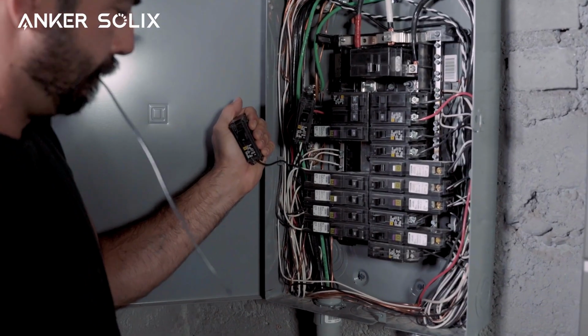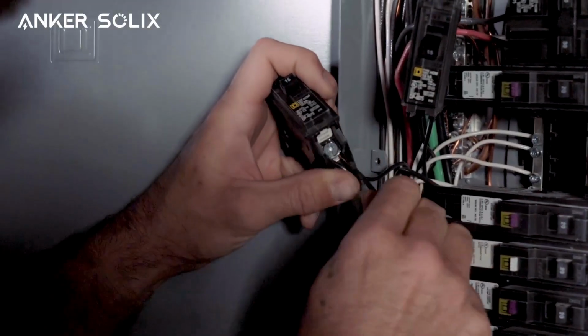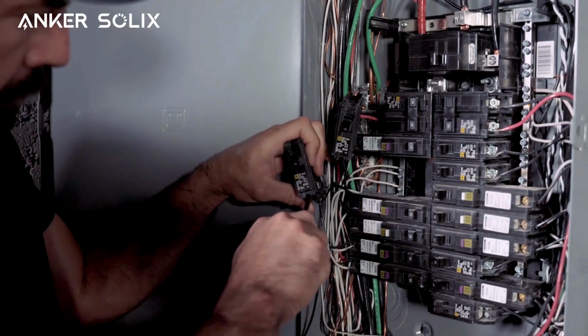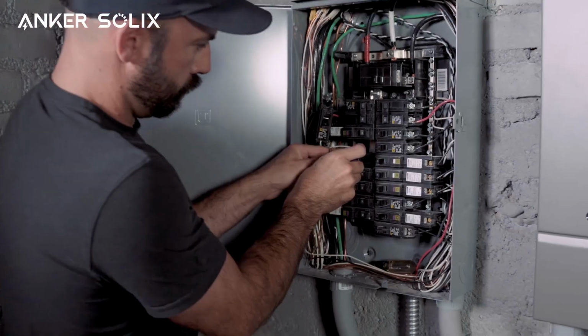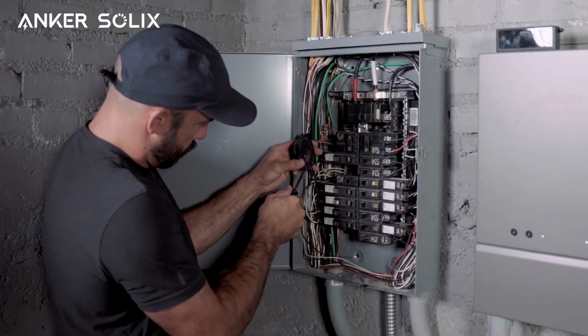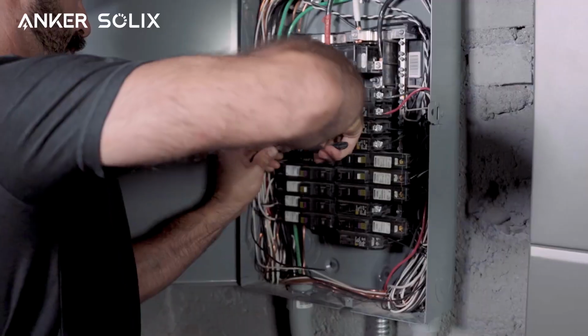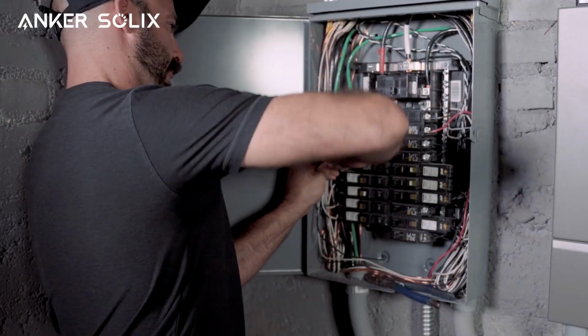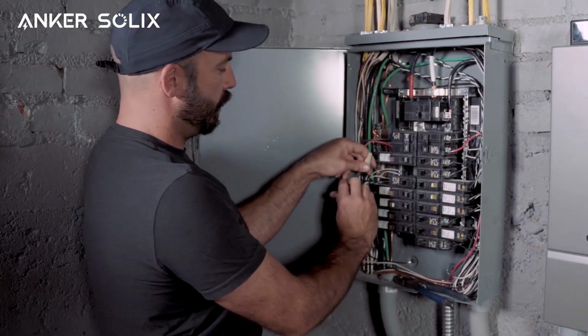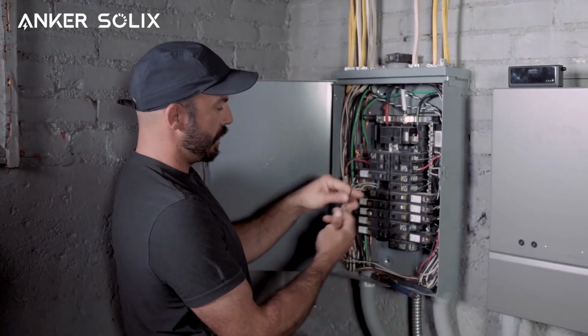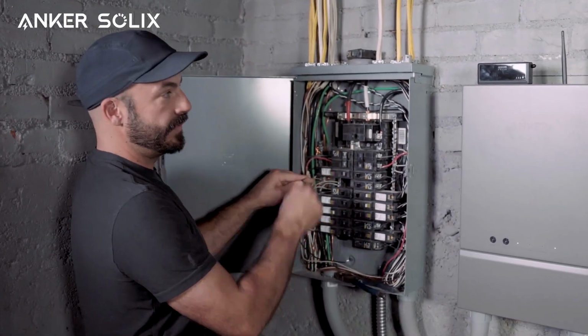So what we'll do is pull one of them out and make what's called a pigtail, creating an NEC approved splice that allows us to tap into this breaker to feed our smart meter. Now we've combined the two wires that originally went into that circuit breaker into one, which frees up a spot on the breaker for the wire that feeds the smart meter.